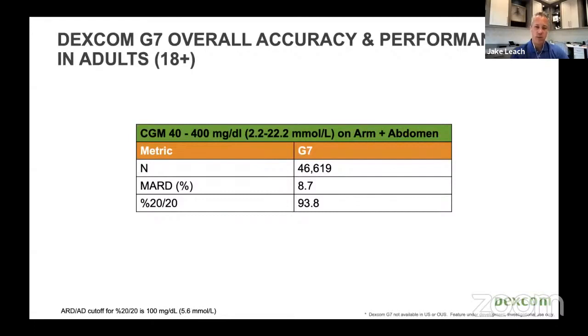MARD is important, but not as important as some of these other metrics. And the iCGM metrics that the FDA put forth to claim that your product is interoperable and meets those standards has a lot of metrics across percent 15/15, percent 20/20, percent 40/40 in all the different glucose ranges, whether it's hypoglycemia or hyperglycemia or euglycemia. So it's all about studying the performance of the device across a lot of different glucose ranges.